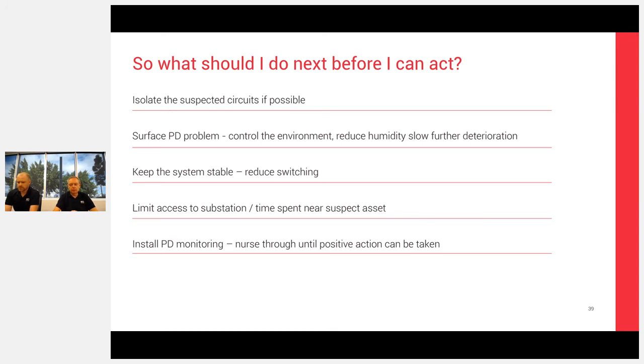And of course, what we've done many times and what people do is install monitoring so you can monitor it through there to see if anything is accelerating away and making changes. As we've said, ultrasonically, that may not always be the best issue, but if you're trying to control the environment, you control and monitor the environment and you see how much discharge is taking place. So they're all the things that we would suggest are put in place until you can ultimately take it off the system and fix it up.